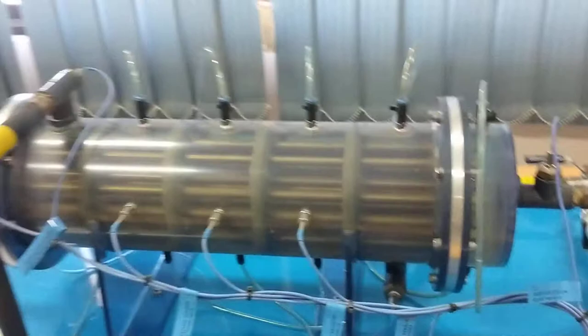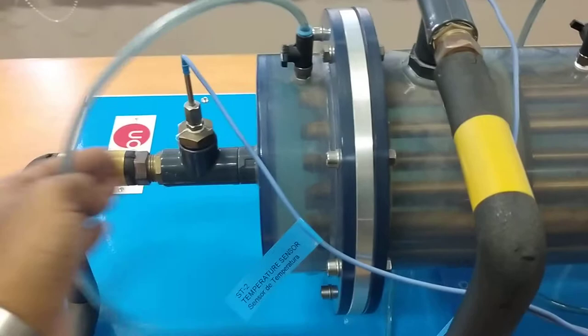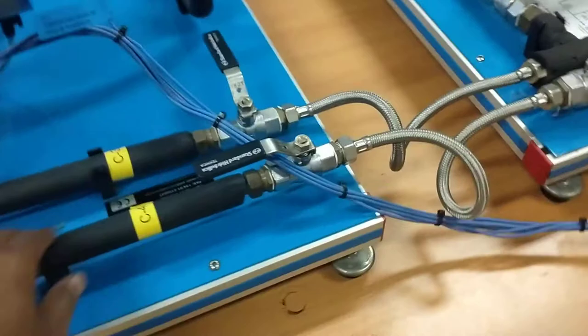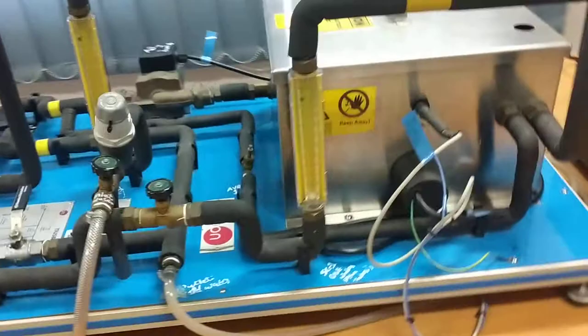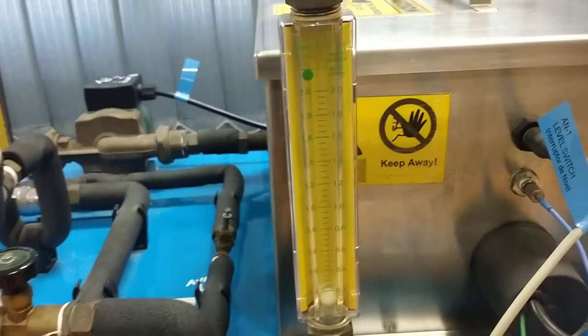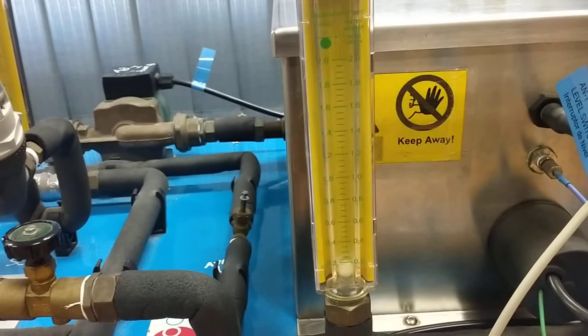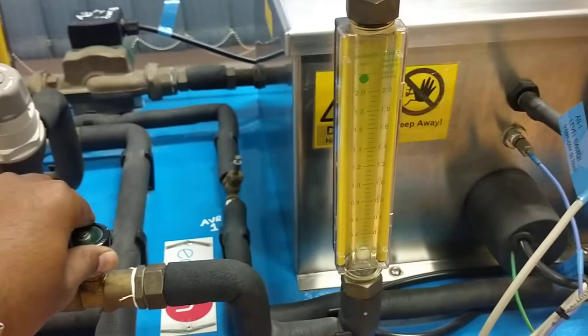The hot water enters through this pipe C1, accumulates in the header, and from here the water moves in the tubes, and then it again collects in the rear header and then moves through this pipe, C4, back to the tank again. You can see the flow meter. This gives the value of the flow rate of the hot water in liters per minute. The maximum value you can read here is 2 liters per minute.